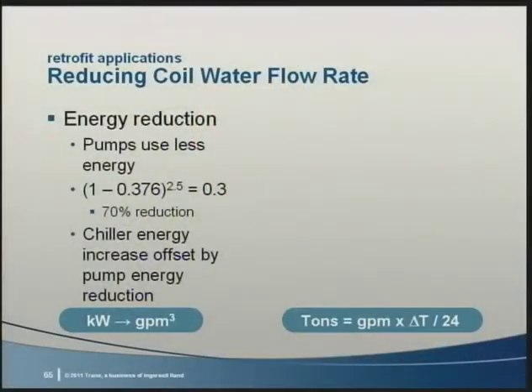This means the GPM has been reduced by over 37% because we've reduced the supply water temperature to the existing coil. Now we'll use this concept in just a minute, but first, let's look conceptually at how reducing flow can help. The pump laws tell us that pump kW decreases with the cube of the flow rate. We need to remember that that's for free discharge systems. In real life, we don't quite achieve the cubic savings. But even if we use the 2.5 power rather than the cubic, the pump power reduction is over 70%.